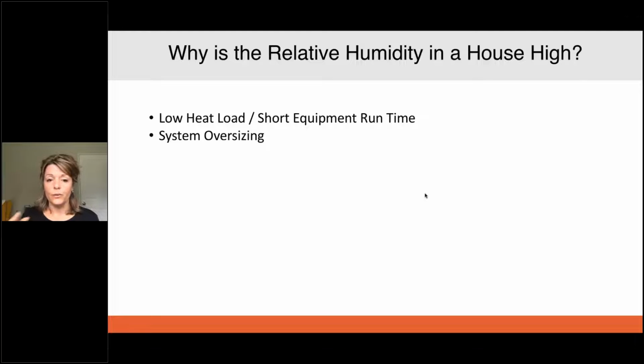Systems are oversized. Even if you're sizing equipment to Manual J best practices, Manual J automatically oversizes by about 15%. Then we have HVAC contractors that oversize on top of that, because we do get some hot times of the year—4th of July, 20 people over for a party, AC's not keeping up, and they don't want the call. So there's a lot of oversizing. I think I saw an article from Joe Lstiburek at Building Science Corp that said we're oversizing our systems by 30 to 50%, which we know, and we're getting better at. But even right-sizing according to Manual J is still a little bit of oversizing.